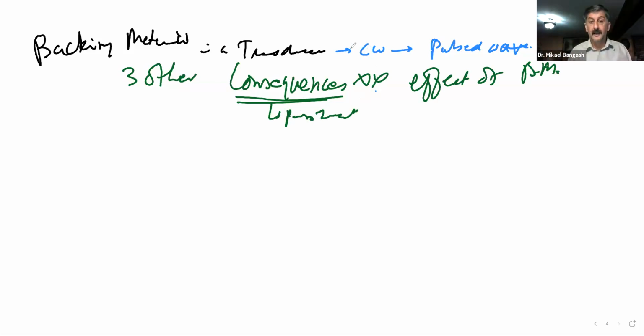Actually, calling that, the sound wave is not going to be continuous, but it could go from continuous to become pulsed. That is one of the major reasons why transducers have a backing material or not. But there are 3 other effects that we get from adding a backing material to a transducer.